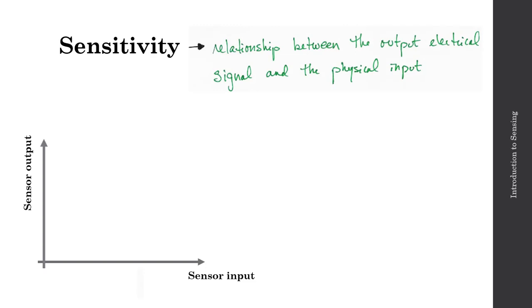Let's begin with sensitivity. Sensitivity describes the relationship between the output signal, which is typically electrical, and the physical input. The sensitivity is often described as a ratio of the change in output relative to the change in input. So you might see something like ohms per lux or volts per meter per second squared. This would be typical of an accelerometer.